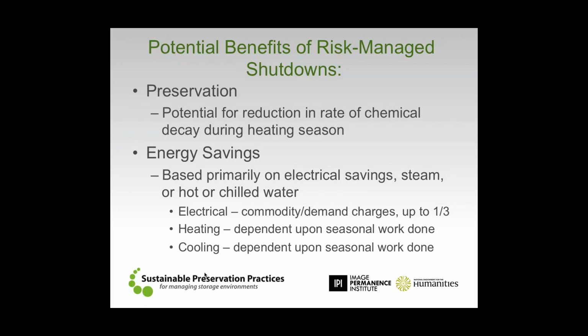Now the other thing about shutdowns to keep in mind is that they can be of whatever length that you want, and any length that the system is turned off is going to be of benefit in terms of energy consumption. So if you're in a hot and humid environment where you only want to try a 2-hour shutdown at night to see how everything responds, well, then give or take, and this is roughly linear, if you shut down for 2 hours, you should be able to save roughly 1/12 of the total energy over the course of a year. So keep in mind that the potential is certainly there, and it's worth thinking about and experimenting with in a risk-managed approach.